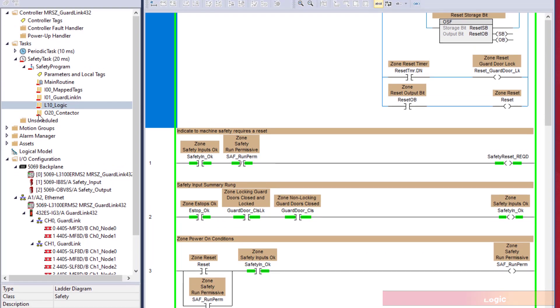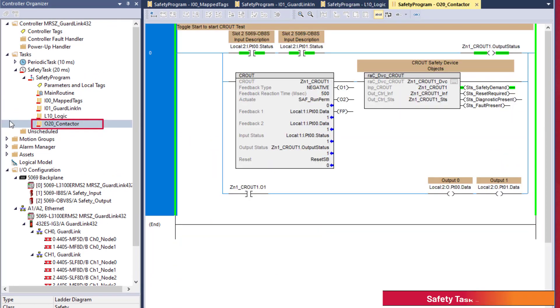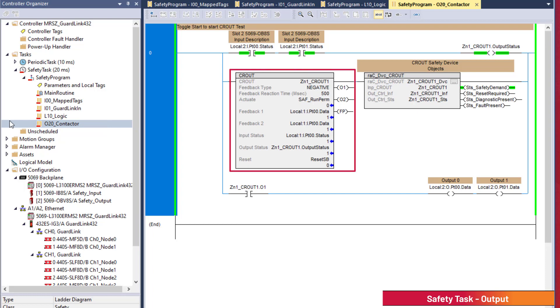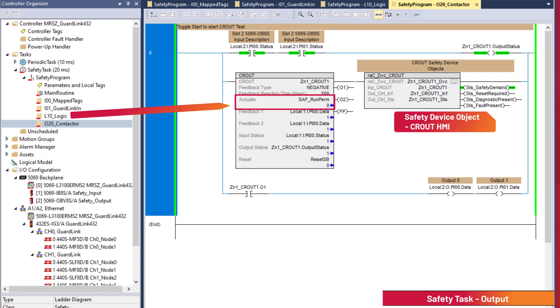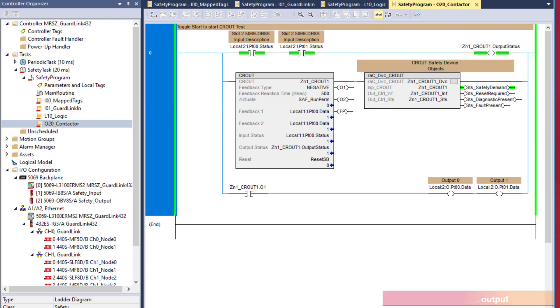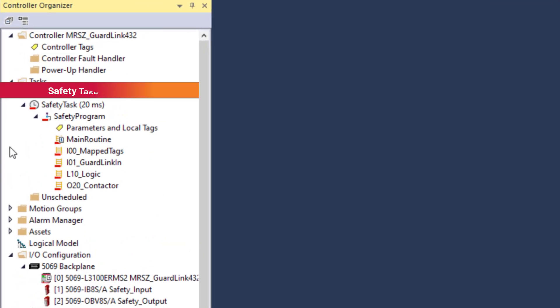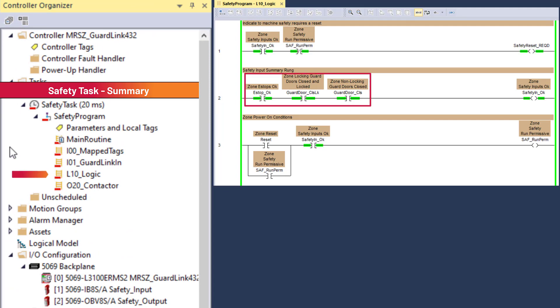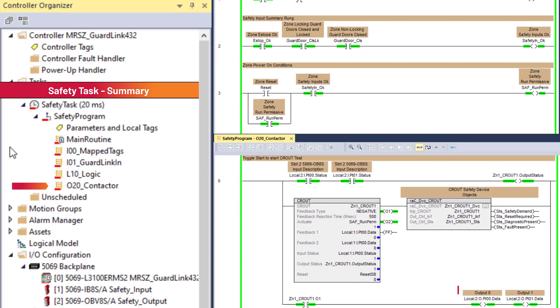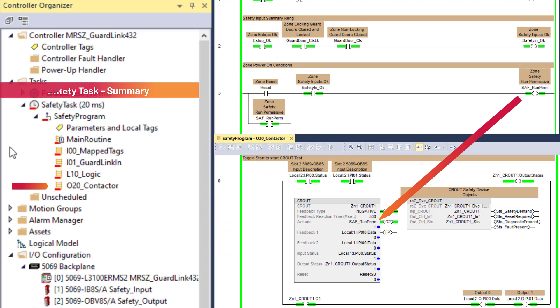Double-clicking on the O2-0 contactor routine, rung 0 has a configurable redundant output instruction that controls a pair of safety contactors. The actuate signal for CROUT is the safety run permissive from the logic routine. To summarize the safety logic: GuardLink channel inputs are combined in the safety input summary. Reset enables the safety run permissive, which energizes two safety contactors. The loss of any GuardLink channel will de-energize the contactors.